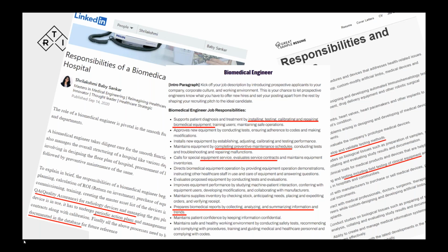And what is that? Well, in the biomed team, they contribute to the safe use of X-ray equipment, to train local staff, and to make sure that everything is up and running and works as it's supposed to. So that's preventive maintenance as well. Some also do repairs, and that would then be the first line repair before the manufacturer or the third-party service organization comes in and does the larger repairs. QA testing, some of that falls onto the shoulders of the medical physicists, but some parts of it also fall under the responsibility of the biomedical team.